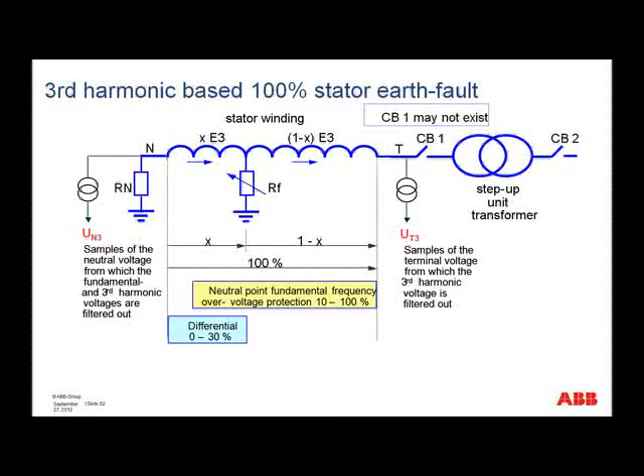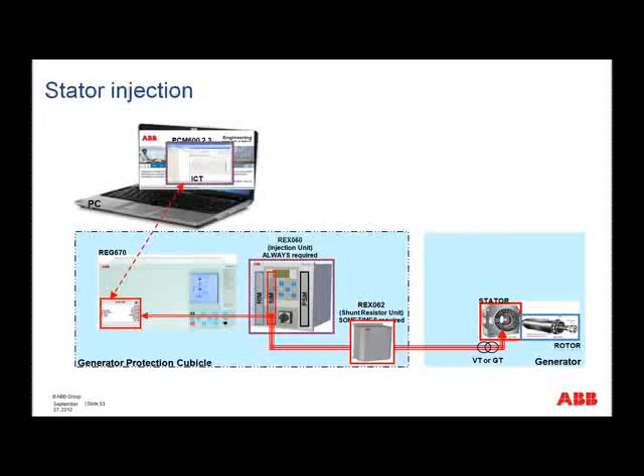So there you see you have the one fundamental frequency protection is covering from about the 10% mark up, and the third harmonic differential is covering from the 0 to about 30%, and by using these two together, we then achieve the 100% stator earth fault. Now, that's the third harmonic principle. It is also possible, as I said, to use the injection, and here you would need, of course, then to get the injection unit, and you would need to couple this injection unit to the point, this is at the neutral point where you would connect it to the stator, and you would also then, of course, need to connect it to the IED. So the IED would then, based on the quantities it receives, then make a determination whether the stator has a ground fault or not.